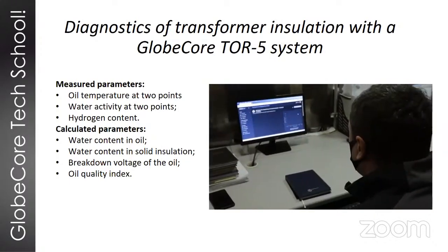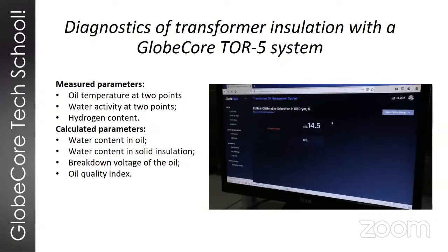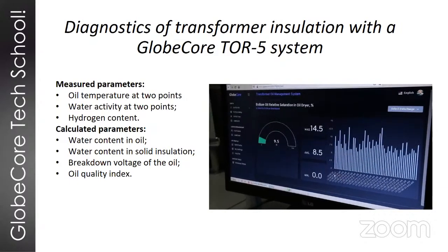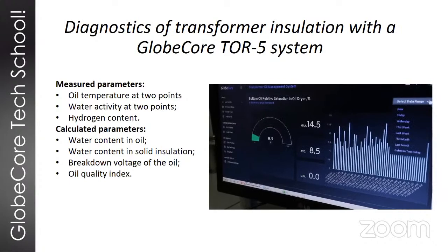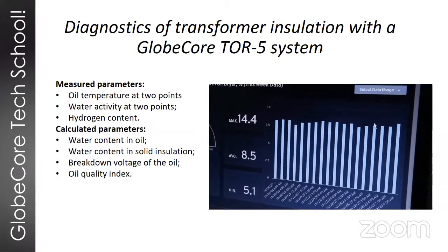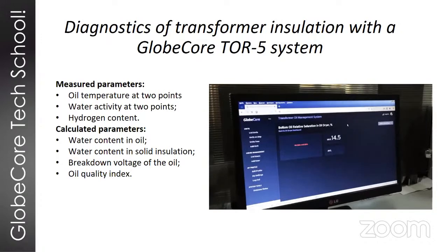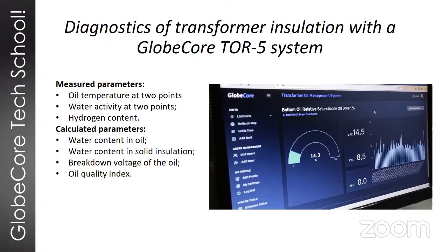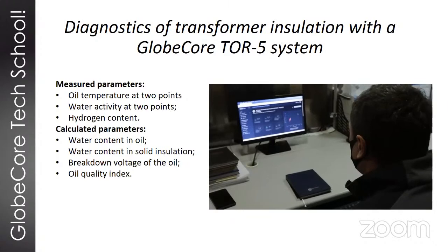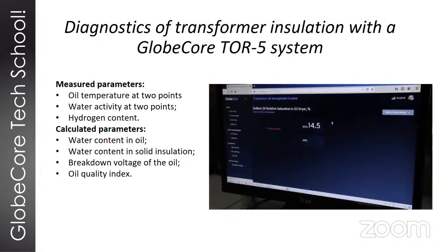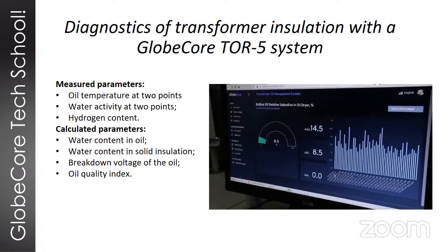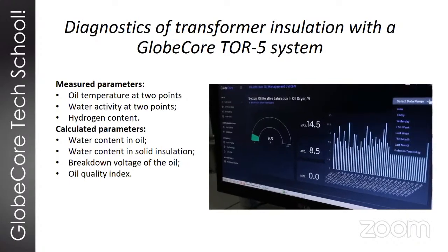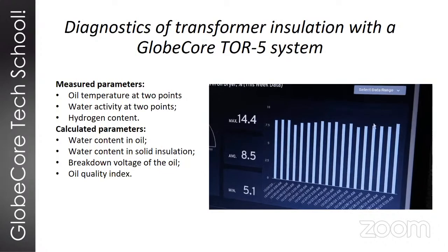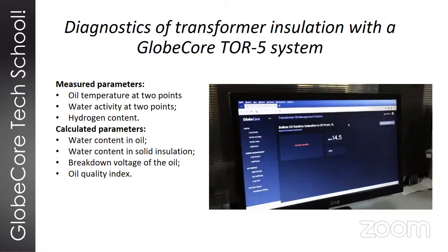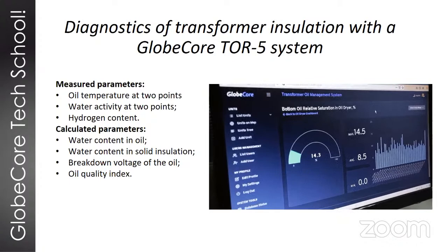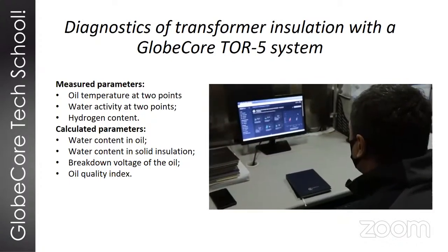So the number of parameters, the amount of information that we have access to through the TOR5, is actually more than the number of sensors we have. And this is done by using some clever calculation algorithms. A lot of the parameters allow us to go outside the limits of simply estimating water in transformer, humidity in transformer, and go to estimation of risks that are related or connected to the amount of water in the oil or in the solid insulation.